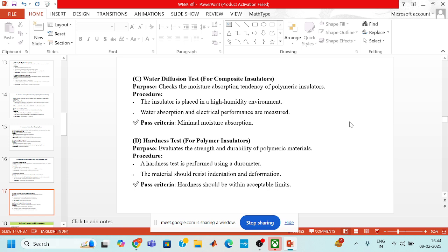Now, the fourth one is the hardness test. The hardness test is done for polymer insulators. It evaluates the strength and durability of polymeric insulators. The procedure is that a hardness test is performed using a durometer, and the material should resist indentation and deformation. If the hardness is within the acceptable limits, then the insulator will pass the hardness test.